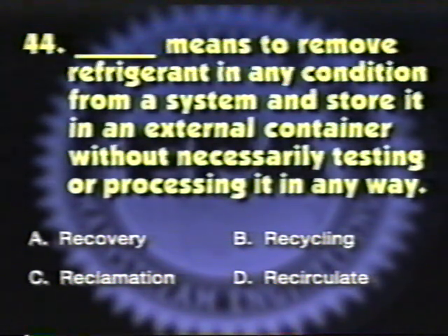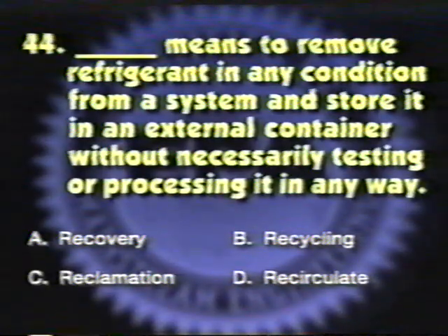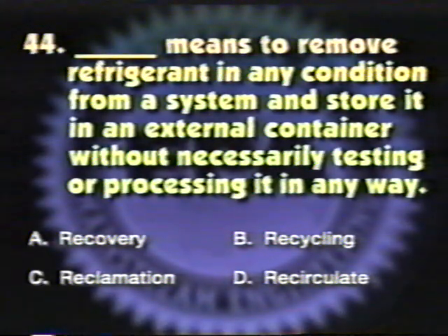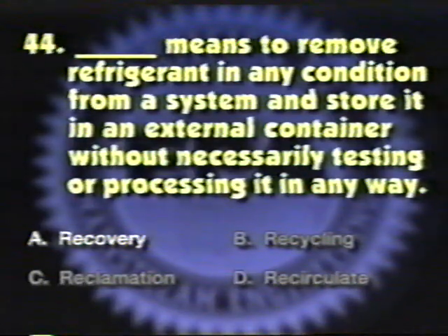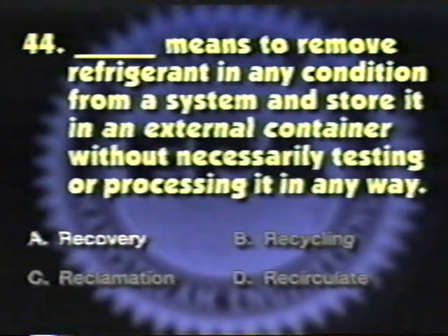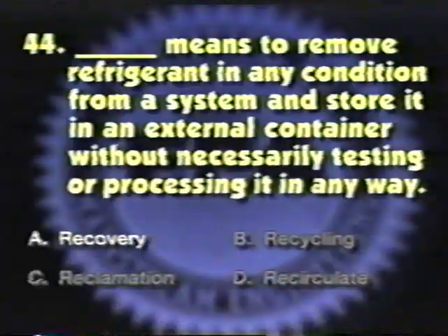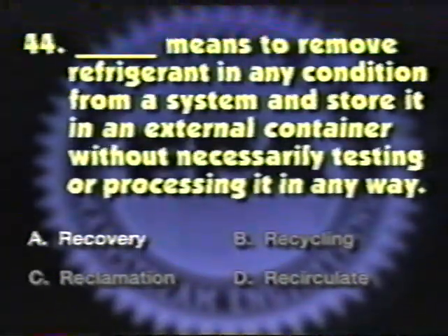D. Recirculate. The definition of recovery is to remove refrigerant in any condition from an appliance and to store it in an external container without necessarily testing or processing it in any way. So the answer is A. Recovery.